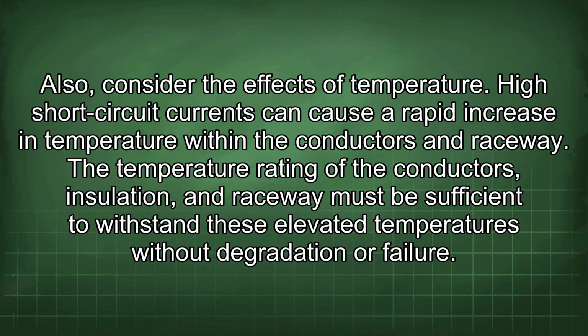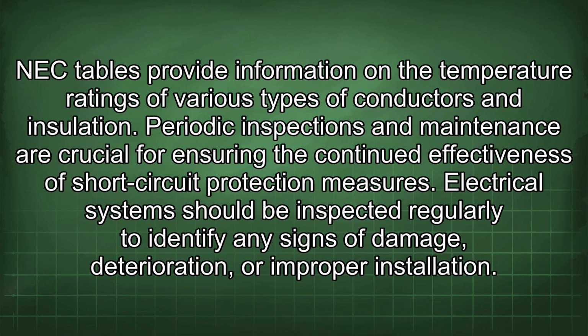Also consider the effects of temperature. High short-circuit currents can cause a rapid increase in temperature within the conductors and raceway. The temperature rating of the conductors, insulation, and raceway must be sufficient to withstand these elevated temperatures without degradation or failure. NEC tables provide information on the temperature ratings of various types of conductors and insulation.